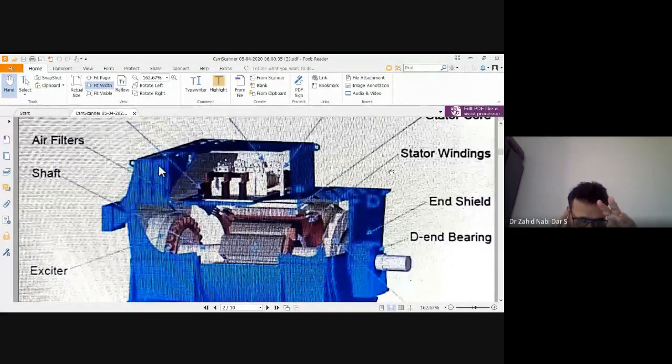This means that the highest voltage between the line would be around 58%, and the stator winding is only 58% of the line voltage. So if the voltage gets reduced, we can reduce the insulation, therefore the amount of insulation in the slots we can reduce, which in turn enables us to increase the cross section of the conductors. A larger conductor permits us to increase the current and the power of the machine.